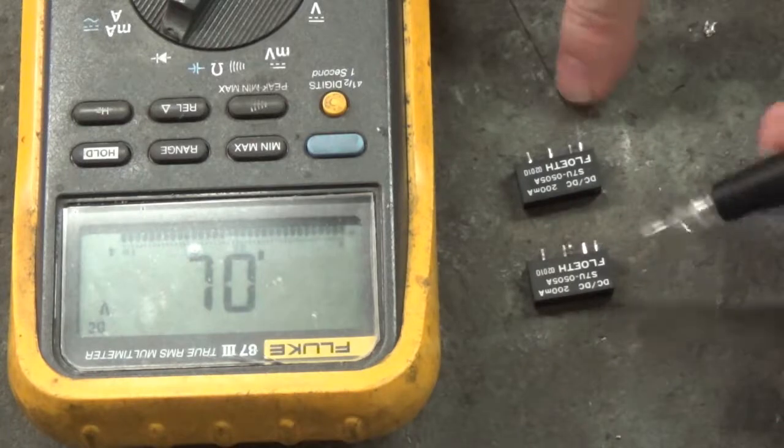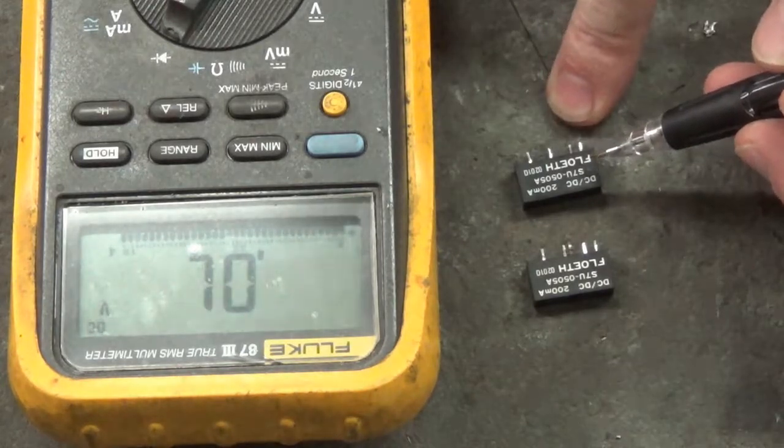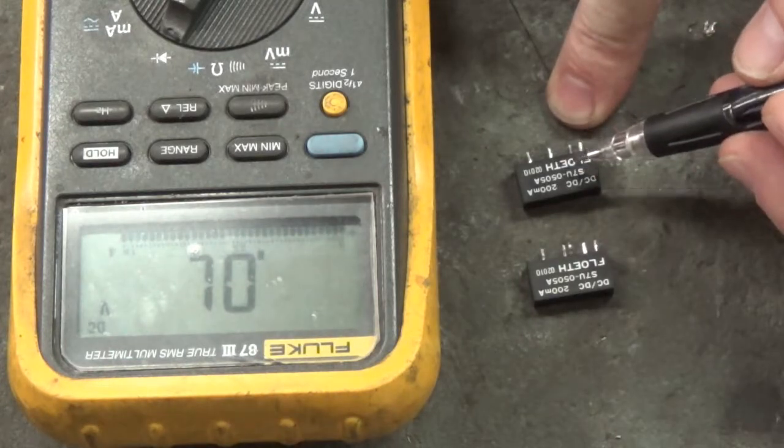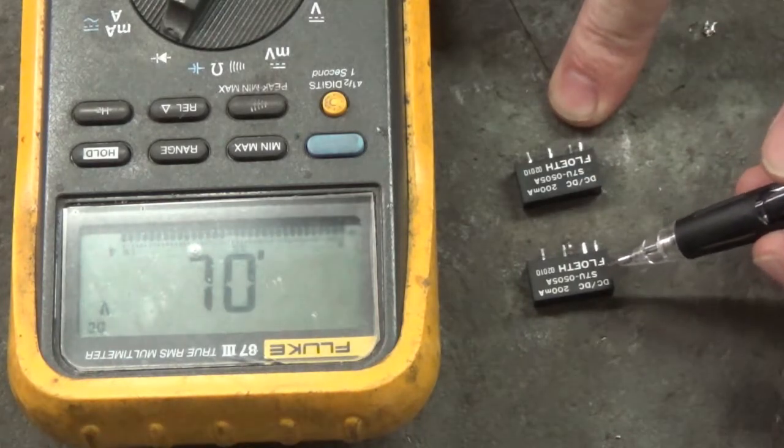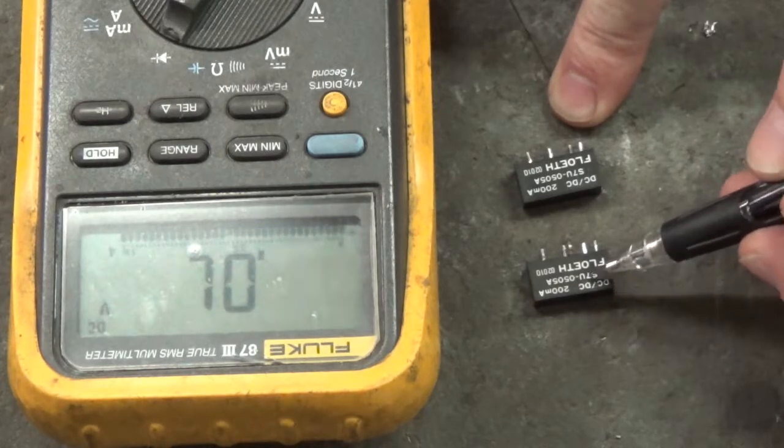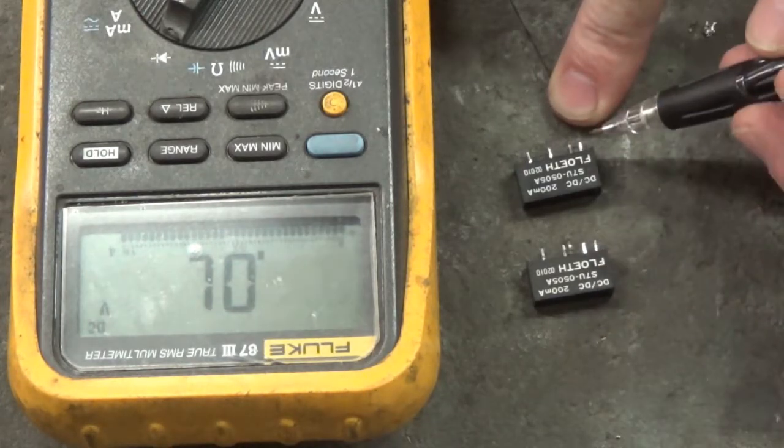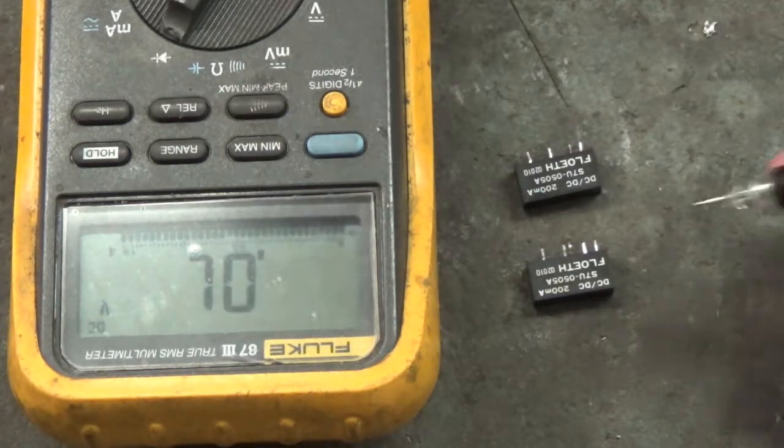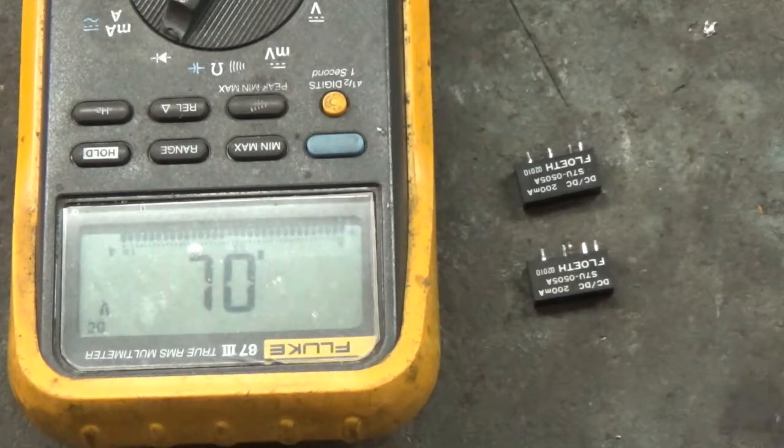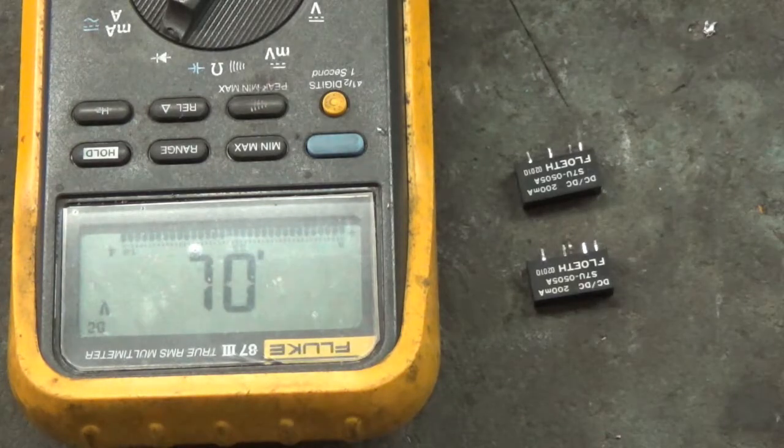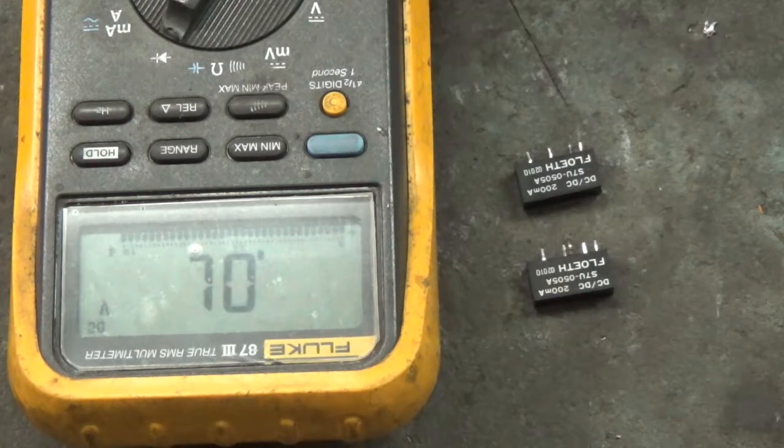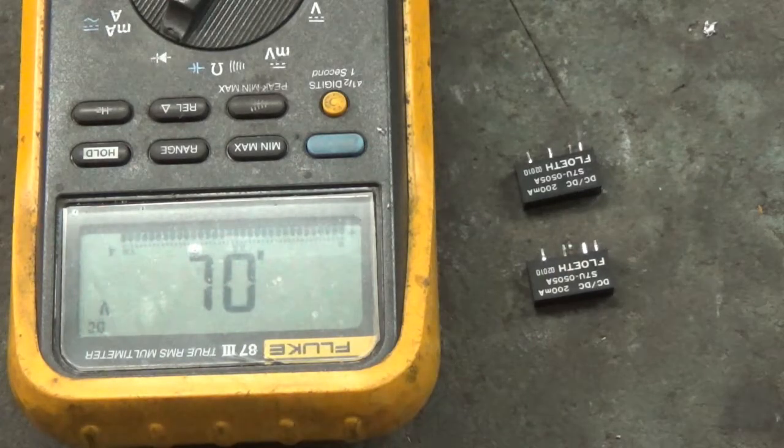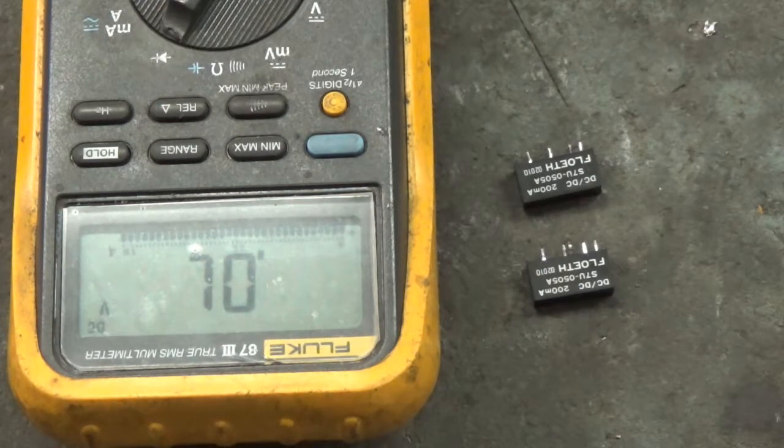I replaced them as a set. Even though this one right here is good, this one died. If I had replaced only one, next week or two weeks or three weeks or a year down the road, this one would have died also, probably in the same manner as this one. That's why I replaced both as a set. After I replaced both these DC to DC converters, I powered up that Siemens profibus DP/DP coupler and it powered up good. I had a good 24 volt green LED turned on.